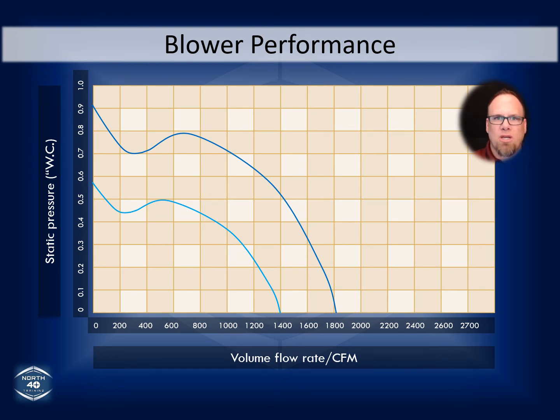Unfortunately, sometimes they're willing to jeopardize their $8,000 or $10,000 install with this equipment on a $30 filter because it's a better filter. These systems were never designed to filter the air. Now, there's a reason you can't go down to your local hardware store and get a filter with the same name as your furnace and a 1-inch filter, because those restrictive MERV 11 filters may not be the best thing for your furnace. So you go down to True Value, you might not find a Goodman 1-inch MERV 11 filter. You might not find a Carrier MERV 11 1-inch filter or a Trane MERV 11 1-inch filter because they weren't designed to be in these systems.